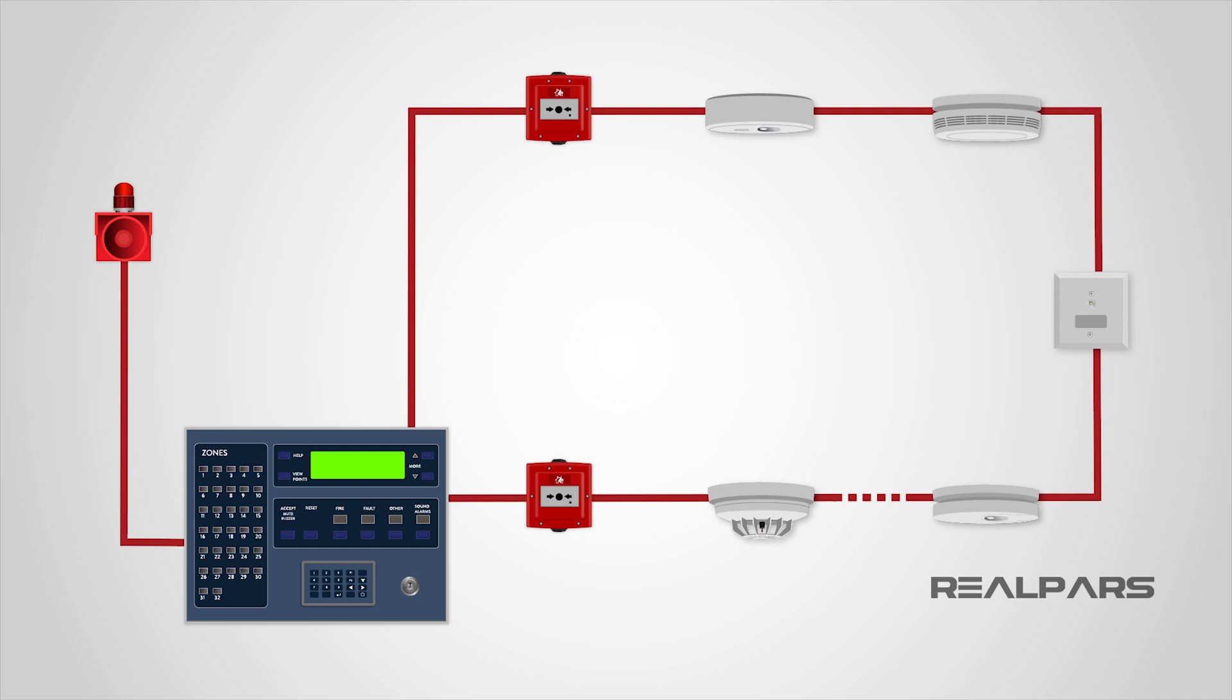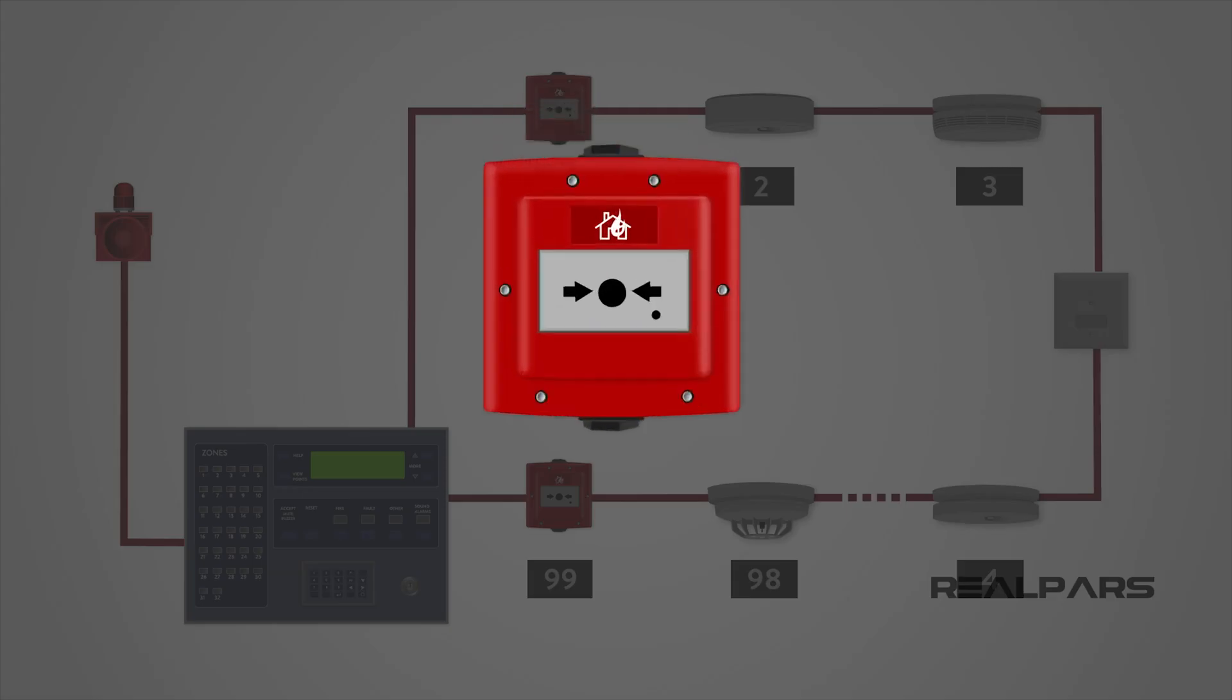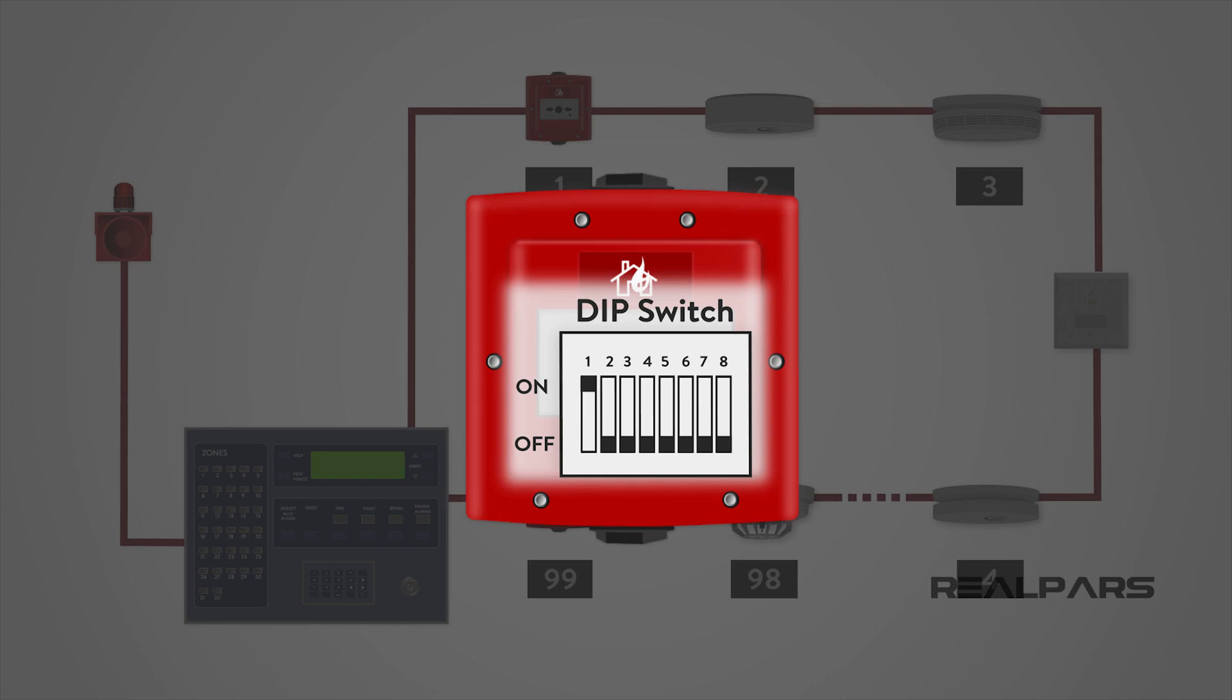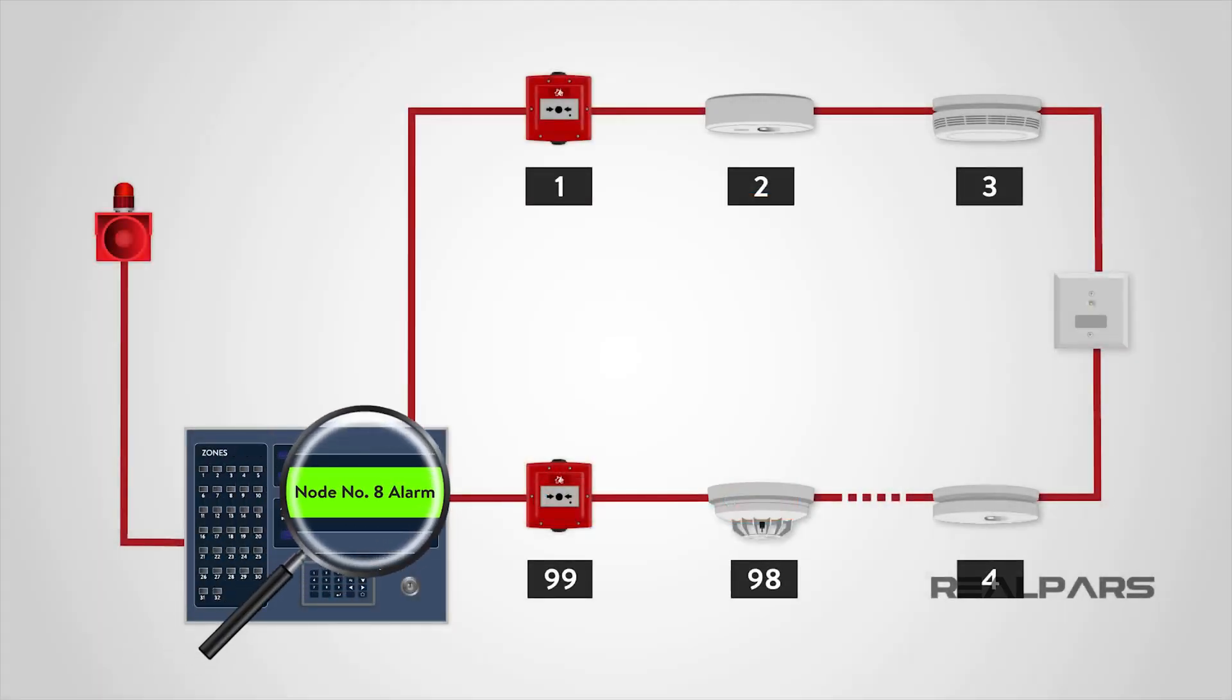The detection principle of an addressable system is the same as a conventional system, except that each detector is given a set address, usually by means of a DIP switch, and the control panel can then determine exactly which detector, or call point, has initiated the alarm.